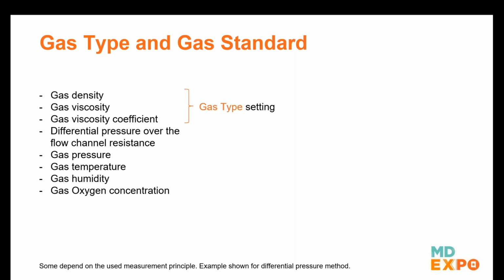But we don't go and say, oh, well, I know the gas density or the gas viscosity coefficient. We just say it's air, okay? Or we say it's oxygen, or we say it's a combination. And the analyzer then knows that that's the gas type we're using. So we want to make sure that whatever gas we're measuring, we tell the analyzer what it is, okay? And you'll see that there are some automatic settings where the gas analyzer uses its O2 sensor to tell you, okay? So there are some that have automatic settings for oxygen.